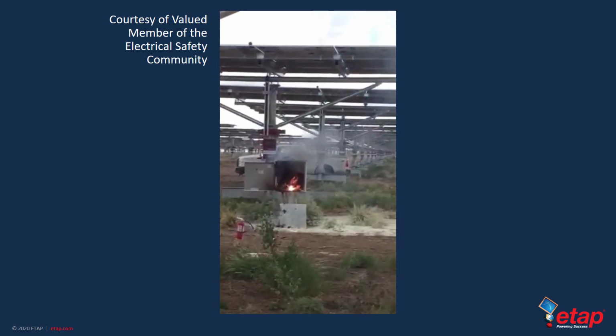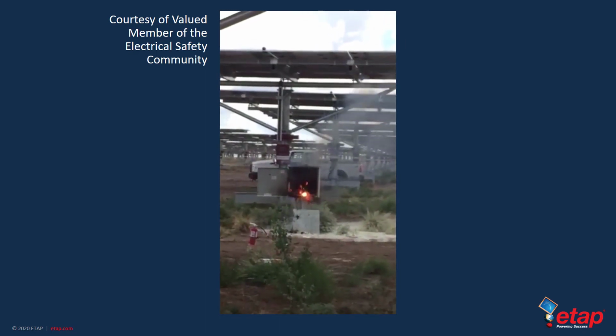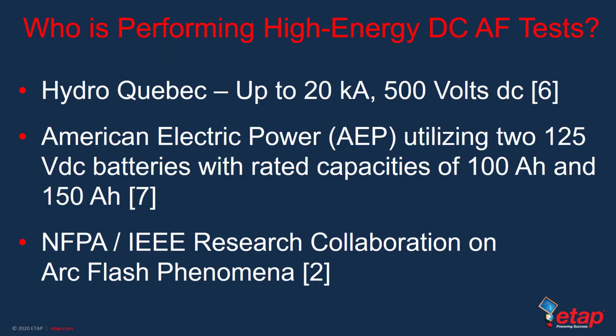Well, to summarize this, the current doesn't seem to be high enough to provide a severe level of ionization energy that is required to generate what we actually call an arc flash, such as an event that we would get in a low voltage or medium voltage industrial size switchgear. Okay, now that we've observed what the energy level and the type of arcs that we get in a photovoltaic system, and now that we know that we have available methods that can allow us to get a far more accurate estimation of the incident energy, yet still conservative, we can now change our gears and look at other types of DC arc flash tests.